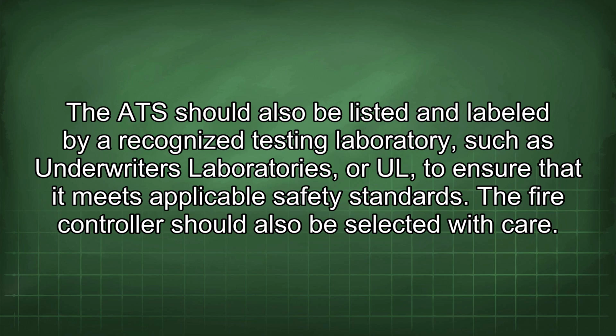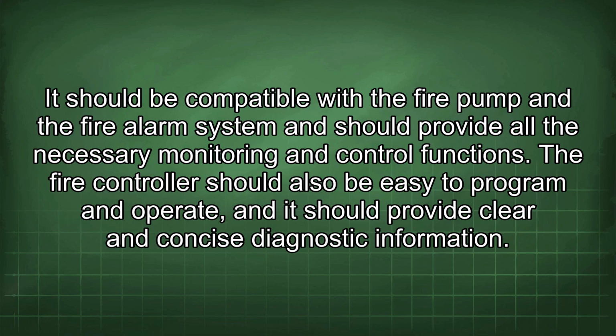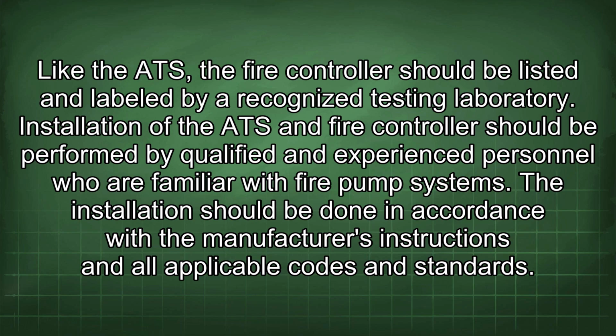The fire controller should also be selected with care. It should be compatible with the fire pump and the fire alarm system and should provide all the necessary monitoring and control functions. The fire controller should also be easy to program and operate, and it should provide clear and concise diagnostic information. Like the ATS, the fire controller should be listed and labeled by a recognized testing laboratory.